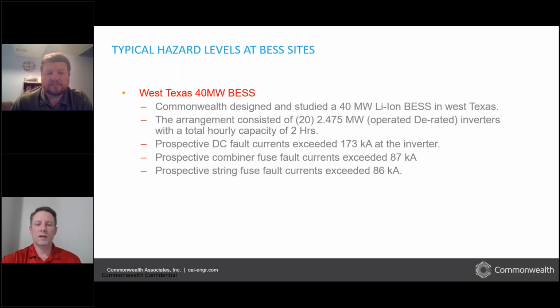So we were seeing 173 kA at the inverter on the DC side, and the fuses that had to break that current were seeing about 86 or 87 kA. It's just hard to find fuses that can even handle that. But we worked with the manufacturers, and I think we got them uprated so that they could.